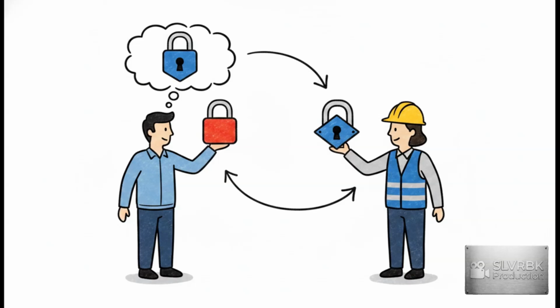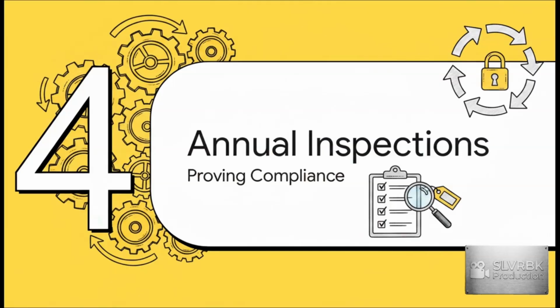And here is the kicker that trips a lot of companies up. The on-site employer is actually responsible for making sure their own team understands and complies with the contractor's safety program. If they use a different colored lock or a specific tag, your local team needs to know exactly what that means and steer clear. Section 4. Conducting annual LOTO inspections, proving compliance.